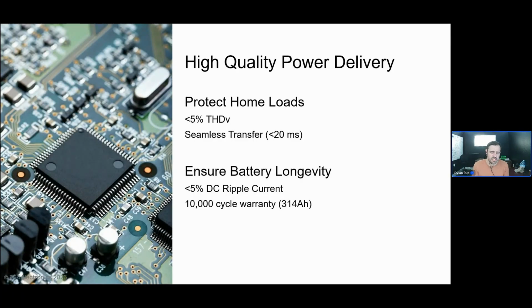Less than 5% of total harmonic distortion. For those of you that aren't familiar with that phrase, total harmonic distortion, or THD, is essentially just a measurement of the amount of noise within the AC sine wave that is delivered by a power source. High amounts of total harmonic distortion can damage sensitive electronics or cause other issues in the home. So ensuring that you have low levels of THD is important, again, especially for the more sensitive electronics in the home. And that is what the FlexBOSS inverter delivers.